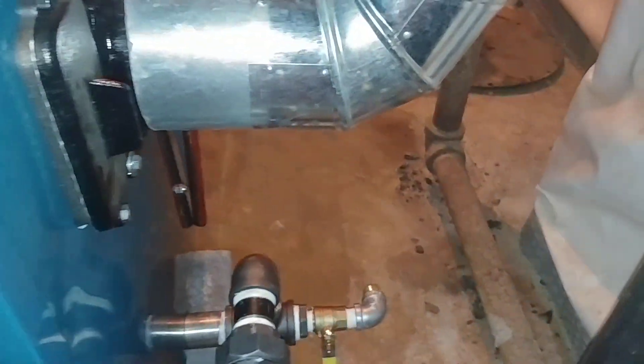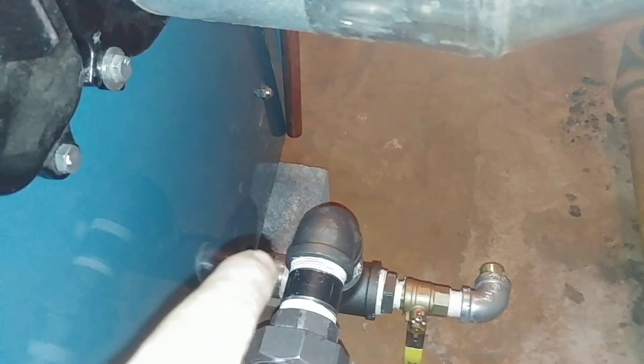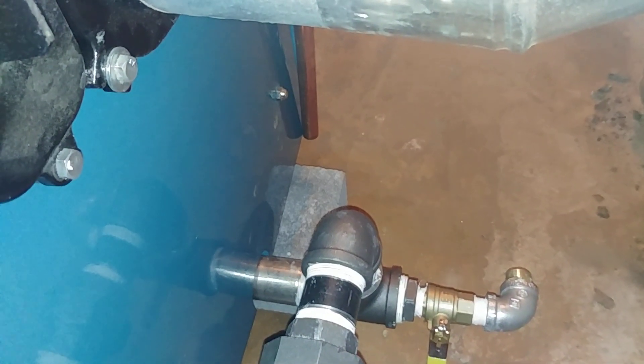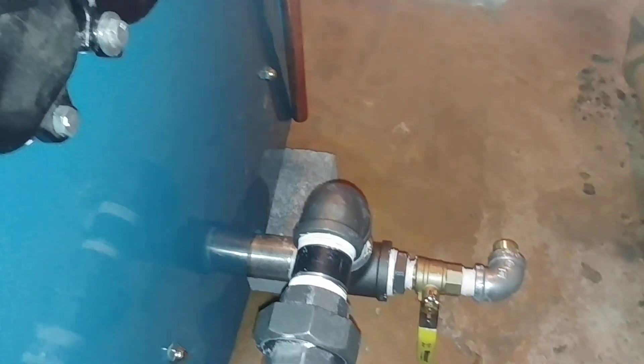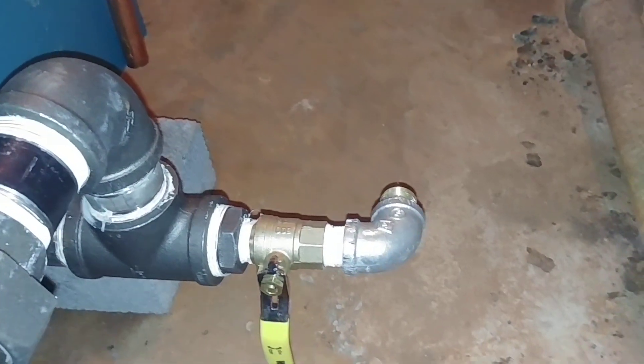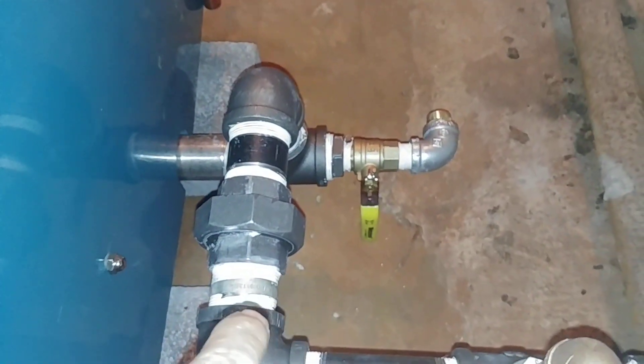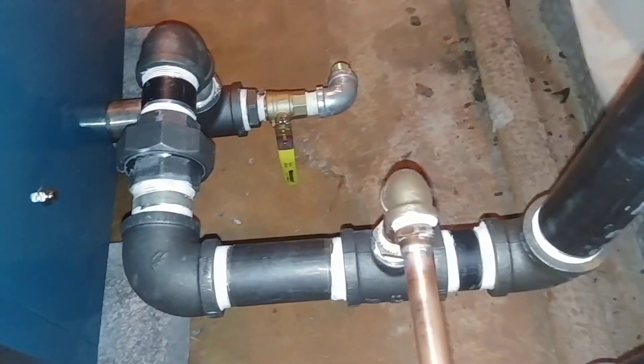This is the return that we did the other day. I've got a stainless steel inch-and-a-half nipple on the return. And we've got a full port drain valve in the back. We've either used extra heavy or stainless steel on this equalizer line.